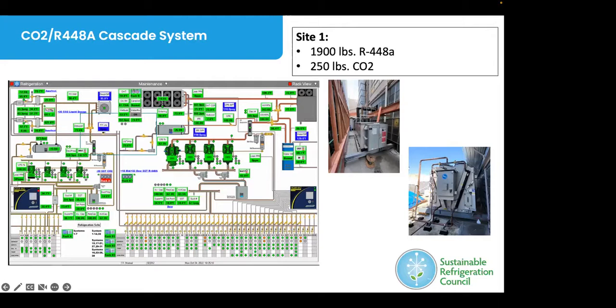and operate these. Again, this was a system where the medium temp cases were not being replaced. So the option here was not just to come in and wipe everything out and go to 100% natural refrigerant. Since the medium temp cases were not in the budget to be replaced, this is set up so that we were able to use a traditional refrigerant system with a DX system off the 448A rack. I think we're going to see that common across a lot of remodels. It's going to depend on what the scope is for the actual cases. Next slide, please.